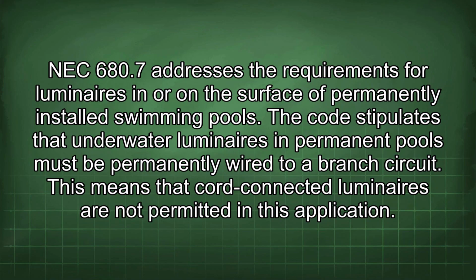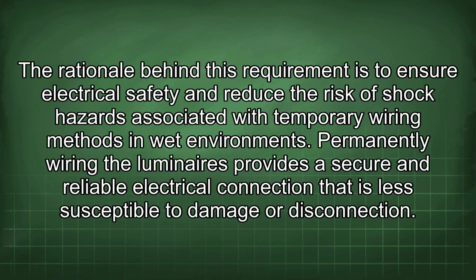NEC 680.7 addresses the requirements for luminaires in or on the surface of permanently installed swimming pools. The code stipulates that underwater luminaires in permanent pools must be permanently wired to a branch circuit. This means that cord-connected luminaires are not permitted in this application. The rationale behind this requirement is to ensure electrical safety and reduce the risk of shock hazards associated with temporary wiring methods in wet environments. Permanently wiring the luminaires provides a secure and reliable electrical connection that is less susceptible to damage or disconnection.